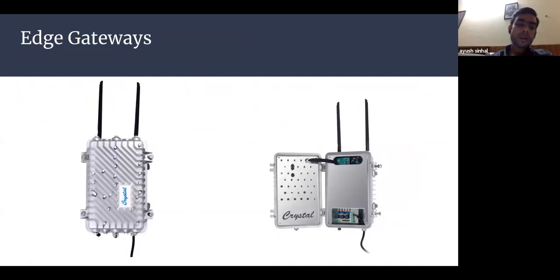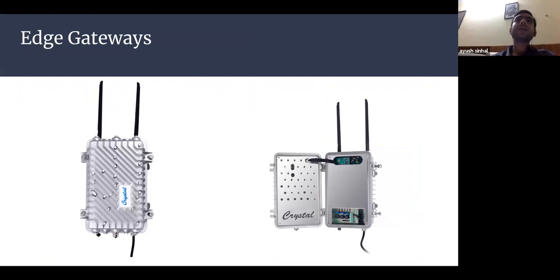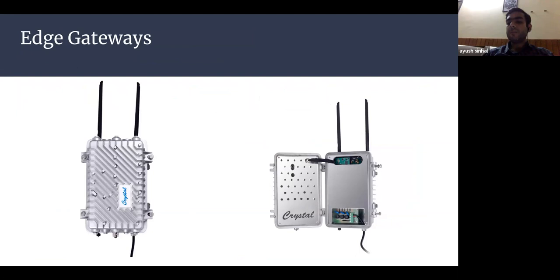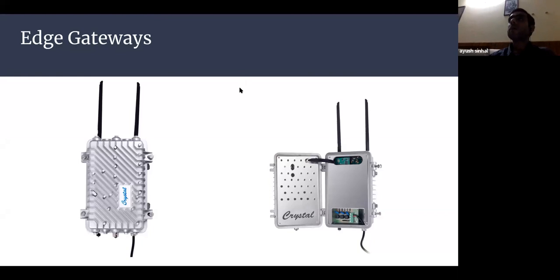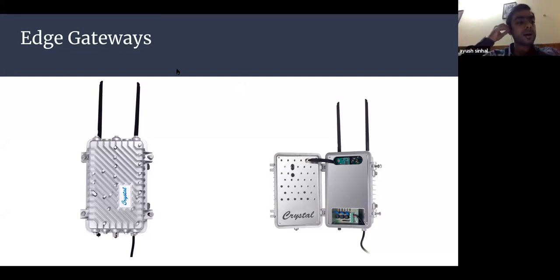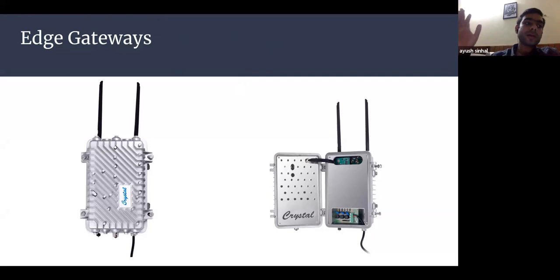Our edge gateway is designed, manufactured by us. It is dual-core with a 1 GHz processor, 2 GB RAM, and around 15 GB of onboard memory. It has 4G connectivity for the northbound and RF for the southbound. It also has a four-hour battery backup and is mounted on a pole. The enclosure is IP65-rated — a rugged device that can endure field conditions continuously for 10 to 12 years.